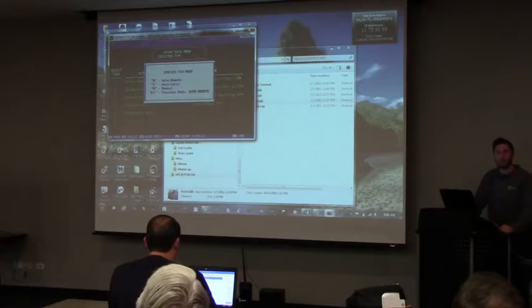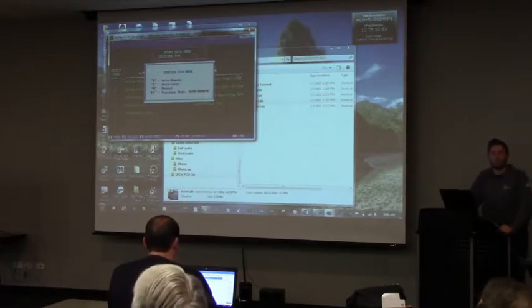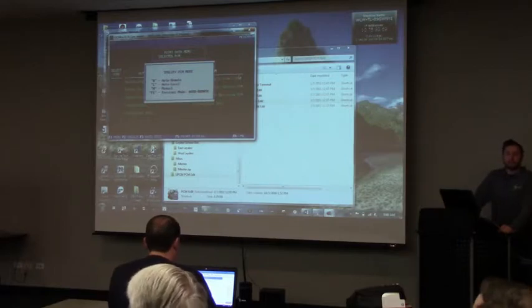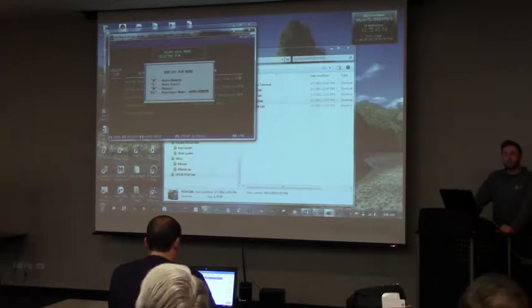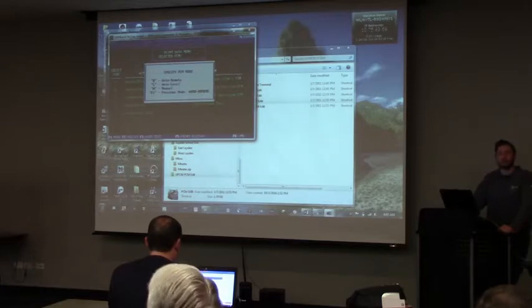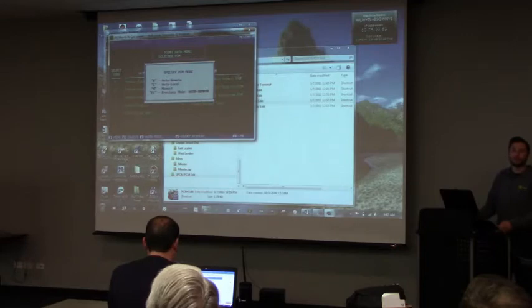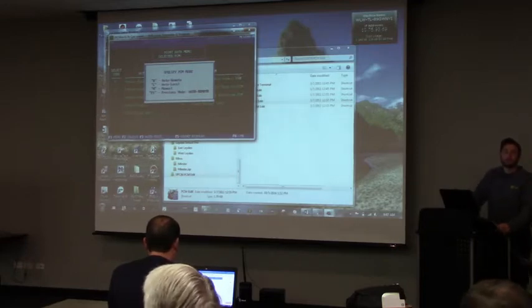Escape. Okay, auto remote means the panel goes into auto, and if there's a higher level BAS, like a Tracer, talking to it, it will take its set points from there. Auto local means it will run all its programs automatically, but it will not be using data from the front end. All your analog and binary set points going to the controller will be controlled at whatever the local value is, the COMLOS value.